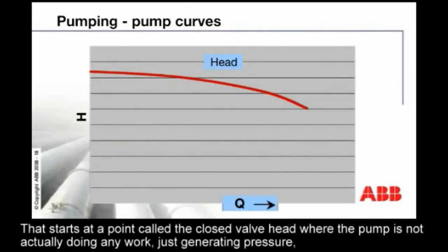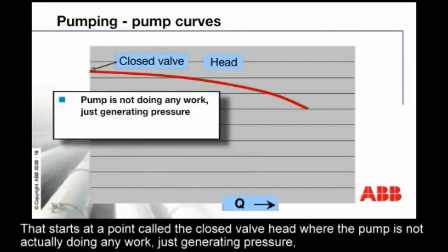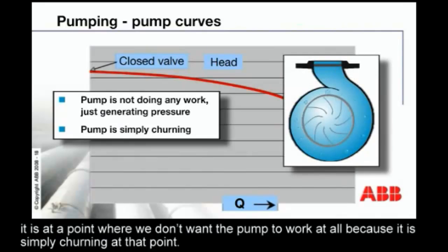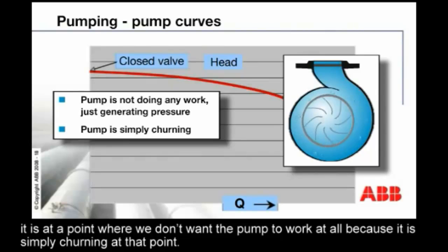That starts at a point called the closed valve head, where the pump is not actually doing any work, just generating pressure. It's a point where we don't want the pump to work at all because it's simply churning at that point.